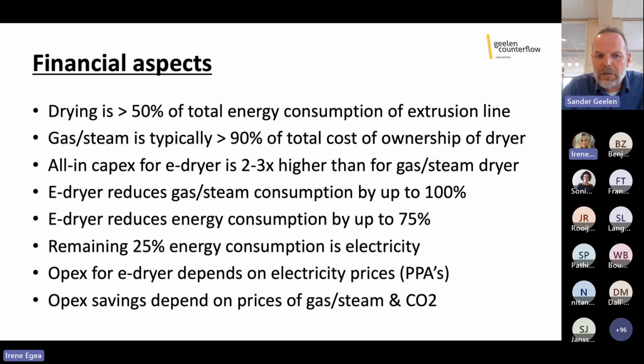Now, the capex for an electrical dryer is significantly higher than for a gas or steam dryer. As you can probably imagine from the slides that I showed you before, there's a lot of complexity involved. It's not only the heat pumps, but it's also the heat exchangers, the control systems, the piping, etc. So the capex side is significantly more expensive, up to 2 to 3 times higher than for a standard gas or steam dryer.